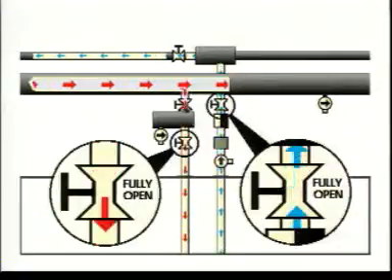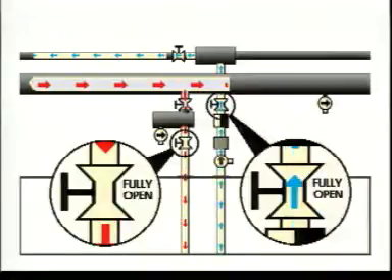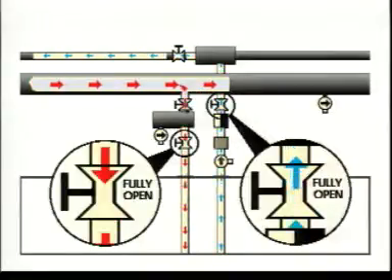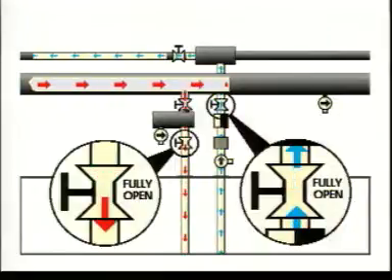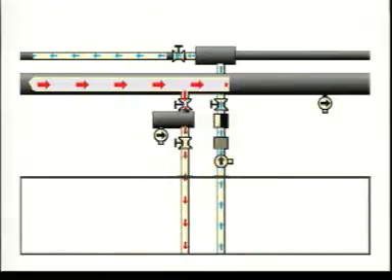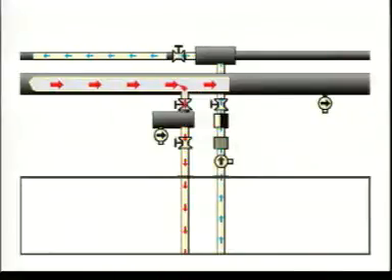Observe that the inlet valve should be fully open. The normal position of the valves is either fully open or closed. You should regulate the heating by the number of coils activated and the main steam pressure. If you need to manipulate the flow, always use the return valve.